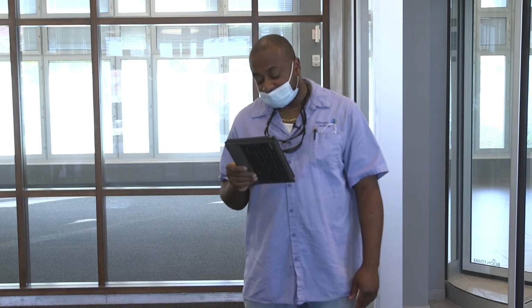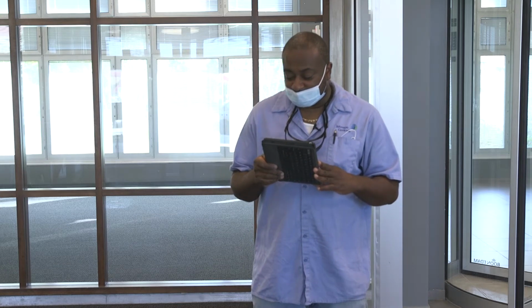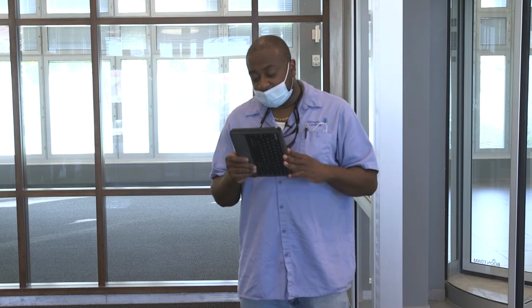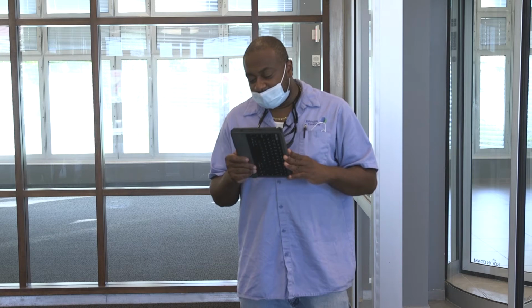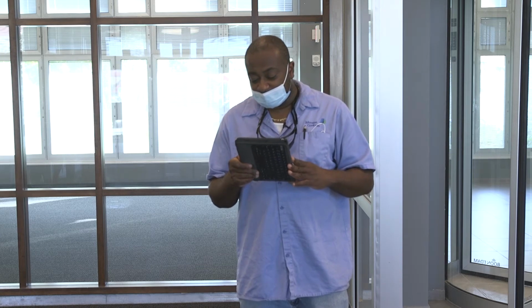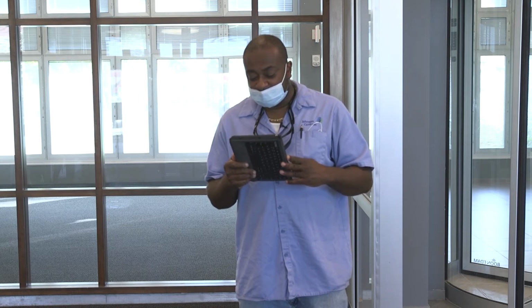Compressor protection. In addition to the external pressure switches, the compressors also have inherent protection. If there is an abnormal temperature rise in the compressor, the protector will open and shut down the compressor.